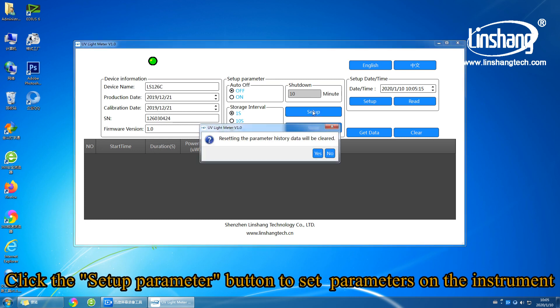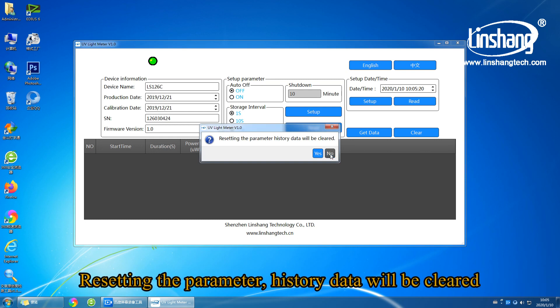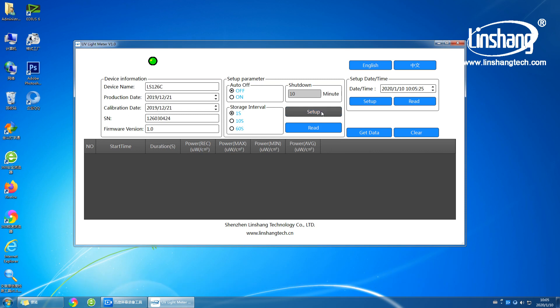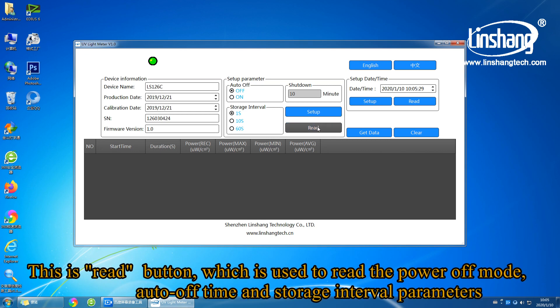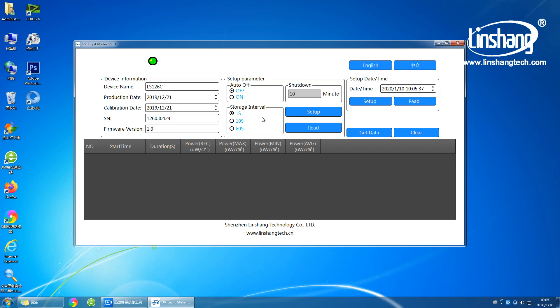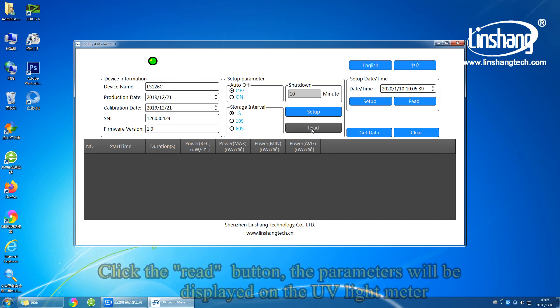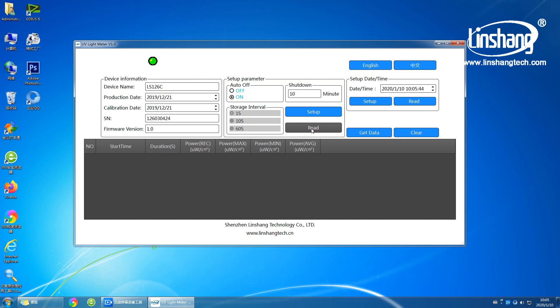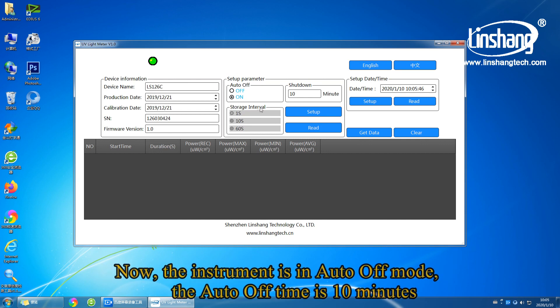Click the setup parameter button to set parameters on the instrument. Note that resetting the parameters will clear the history data. This is the Read button, which is used to read the power off mode, auto off time, and storage interval parameters. Click the Read button and the parameters will be displayed on the UV light meter. The instrument is currently in auto off mode with an auto off time of 10 minutes.